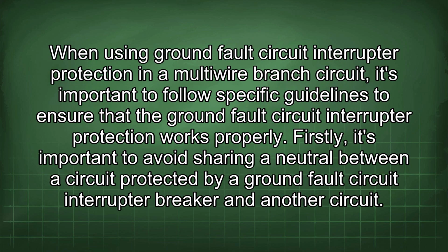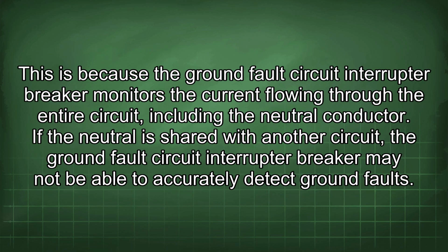When using ground fault circuit interrupter protection in a multi-wire branch circuit, it's important to follow specific guidelines to ensure that the ground fault circuit interrupter protection works properly. Firstly, it's important to avoid sharing a neutral between a circuit protected by a ground fault circuit interrupter breaker and another circuit. This is because the ground fault circuit interrupter breaker monitors the current flowing through the entire circuit, including the neutral conductor. If the neutral is shared with another circuit, the ground fault circuit interrupter breaker may not be able to accurately detect ground faults.